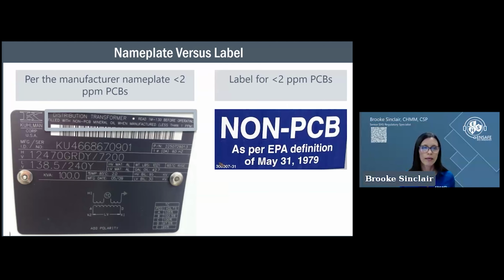I mentioned a nameplate. The nameplate is really key—it comes directly from the manufacturer and will say something like 'contains no PCBs,' or 'less than 2 parts per million PCBs,' or 'less than 1 part per million PCB.' The nameplate you see on the left is different than a label.